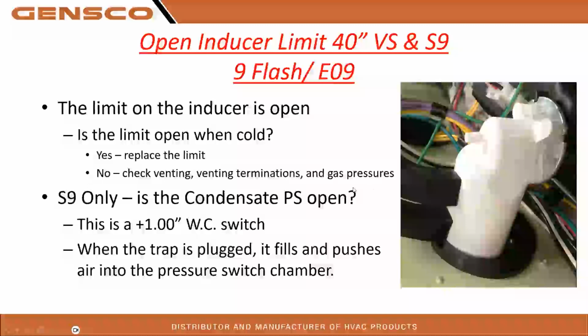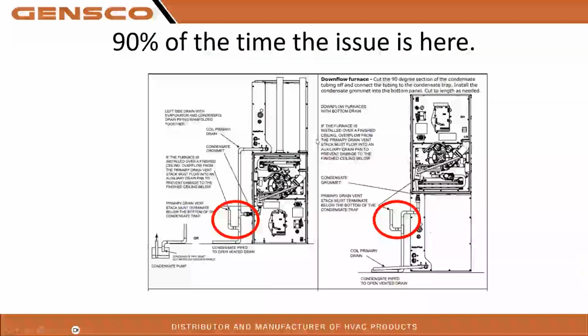On the S9 furnace, you still have a limit on the inducer motor, but it is tied in with the pressure switch that monitors the drain trap here. So that's the condensate pressure switch. It's a 1.0 switch. When the trap is plugged, it fills and pushes air into the pressure switch chamber, which then trips that switch, throwing the E09. I've had calls in to tech before where some technicians say, well, it's been installed for 3 years and now it's having these problems. It's all down to pretty much one situation most of the time, which is this one right here.